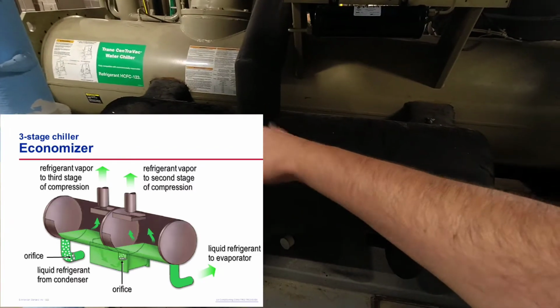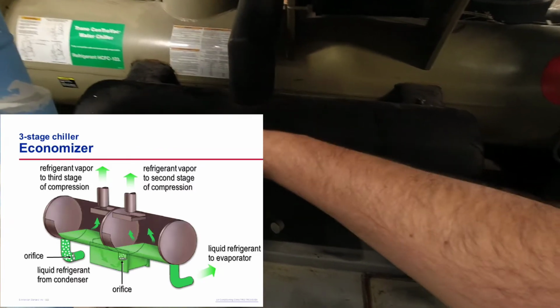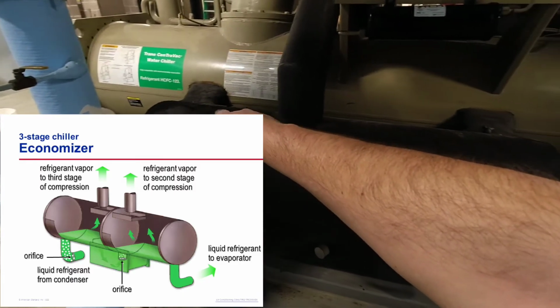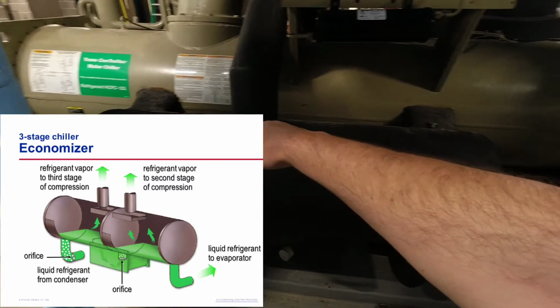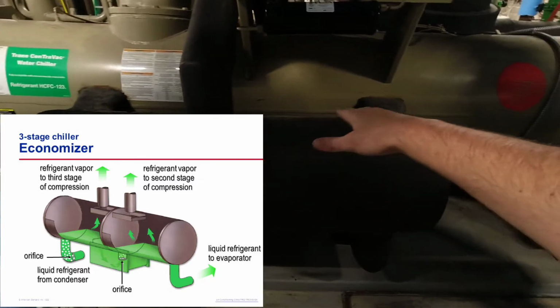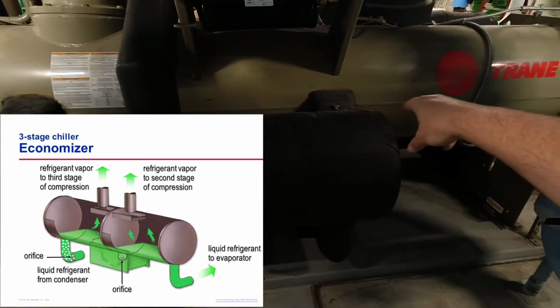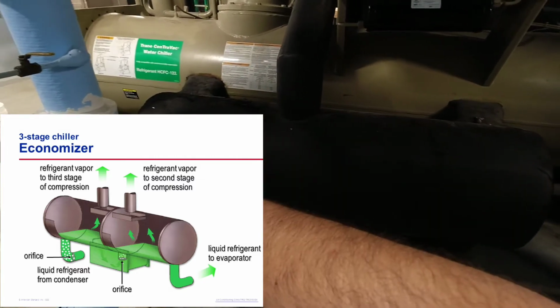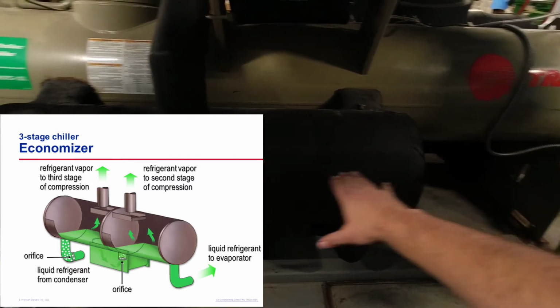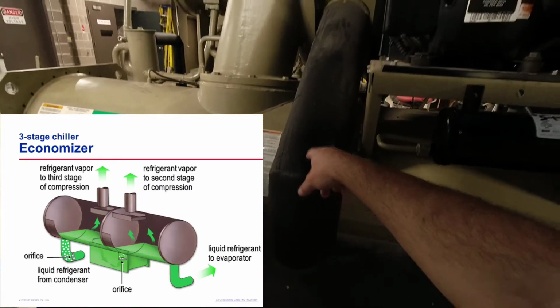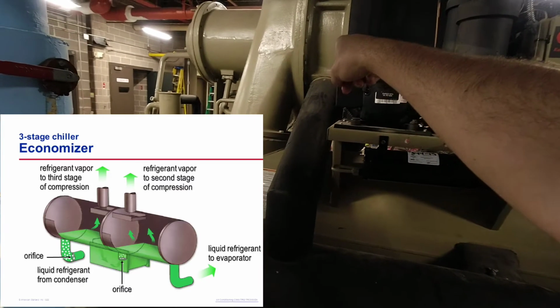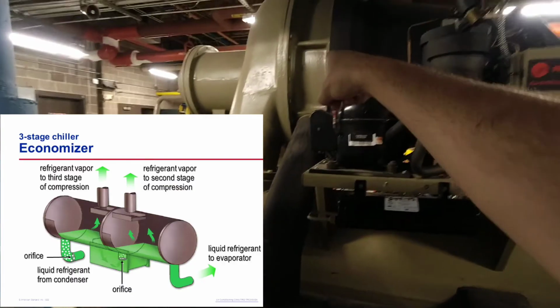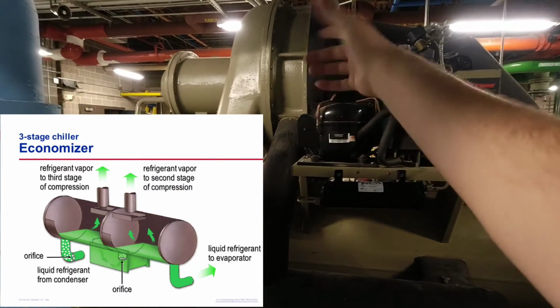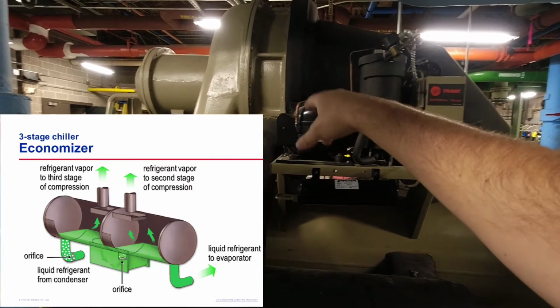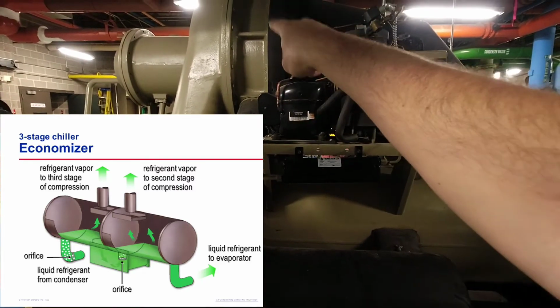Say it's a 20/80 mixture or 25/75, depending on who you talk to. Well, that extra 25 or 20% of flash gas that flashes off gets collected here at the top of the economizer, and all the liquid refrigerant stays there at the bottom. And this line here is the flash gas suction off of the economizer, pulling back into the second stage impeller, or if this was a CVHE, you'd have two pipes coming off into the second and third stage impellers.